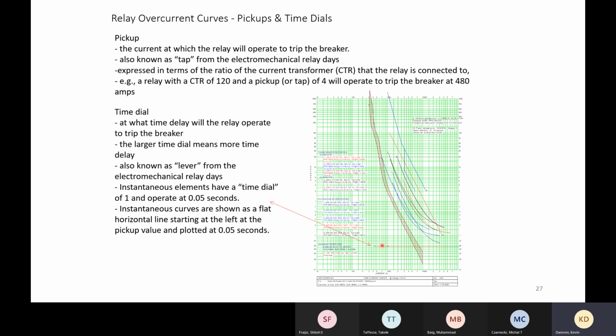The way you read a TCC is you pick a value, say 3000 amps, and follow it up. Well, I'd hit my instantaneous first. And I think it was Michael that said they have those turned on first and then they turn them off. In my utility, we do what's called fuse saving. For an initial fault, we hit the instantaneous element and we trip. Then we reclose. At that point, we turn these off, so now it's not there. So the next operation should be by the fuse.